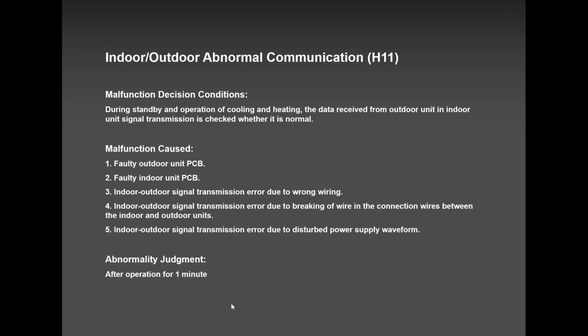H11 has been chosen as the first and a very popular code. H11 is very popular because on a brand new system, definitely you have crossed the wires. Definitely you have crossed the wires. No matter which God you swear on, you have crossed the wires. And if you have not crossed the wires, you have hooked up a condensate pump, and on that condensate pump you cut some wires and made some joints, and that is causing this H11. So please do not cut and join the control wires that are running.